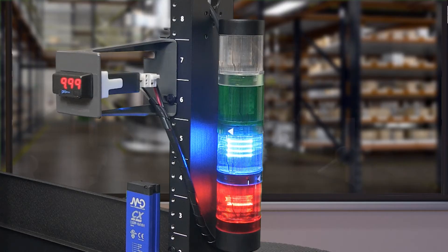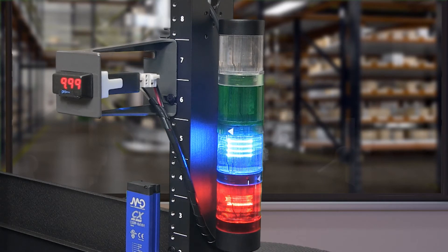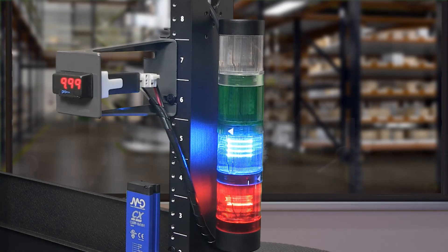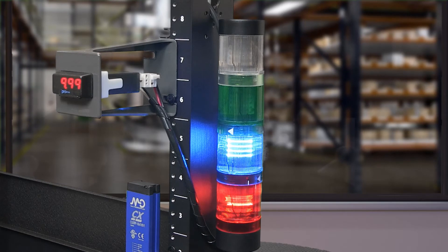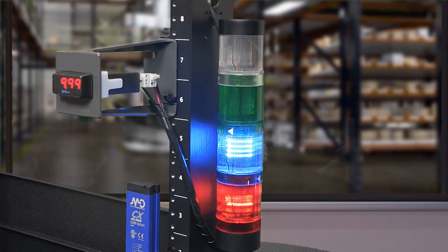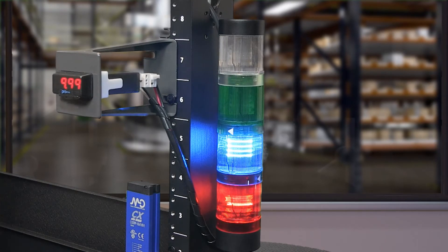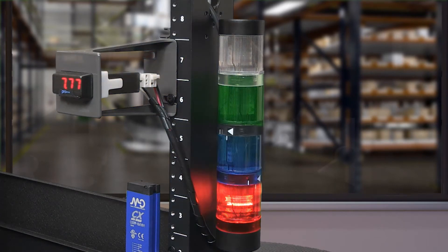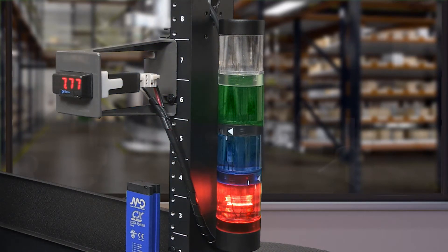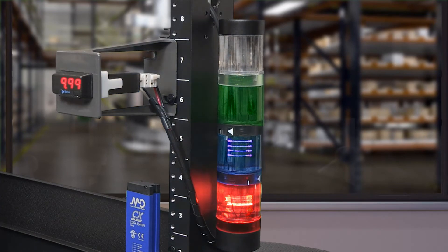In this example, I have the black wire connected to the positive input on a Werma stack light that we sell here at Automation Direct. Make sure you check the specs of your device. I am using an LED indicator because the incandescent light required more current than the sensor supplied, so we would not see an indication.